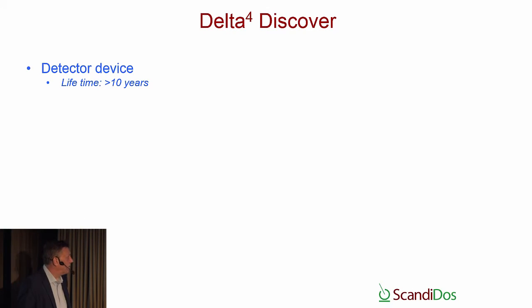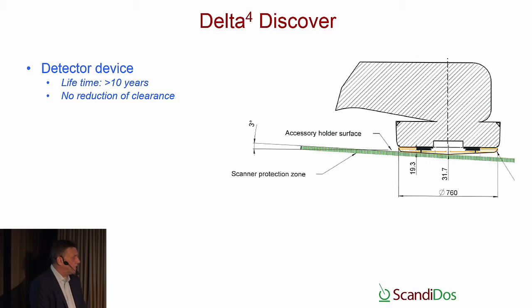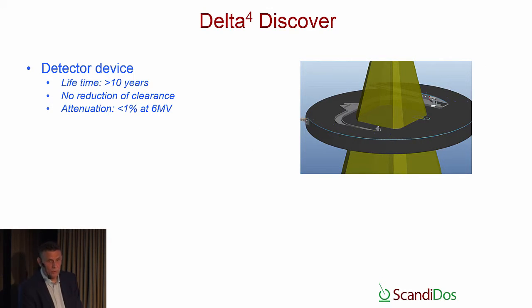If we look into the device, the Delta4 Discover, it has a lifetime that exceeds 10 years. It doesn't provide any reduction in clearance. The profile of the detector is very thin, so it goes in between the laser guard and the treatment head. So it doesn't take away any of the clearance of the treatment, which is extremely important. The attenuation is very small. It's only some carbon fiber and some printed circuit boards that attenuates less than 1% at the 6 MV beam, and it doesn't reshape your profiles or depth doses. No recommissioning is necessary. It's very simple to just put in a small correction for the attenuation.